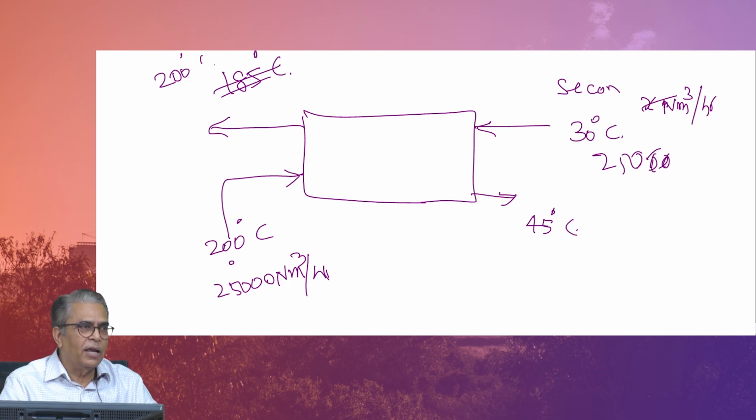So, this material will have a lot of moisture. You will not know what it is unless you do the mass balance of the dryer, but you can figure out it is going to be quite wet. In that wet 500 ppm SO2, as it becomes cooler and cooler, there is a point where it will start condensing, that is the water and SO2 will start condensing, and this is a deadly corrosive material. So, normally unless you go for some fancy material of construction like chronifer, high nickel alloy and all that, people do not cool it down to 45 degrees. So, it is a bit of a cost benefit analysis.